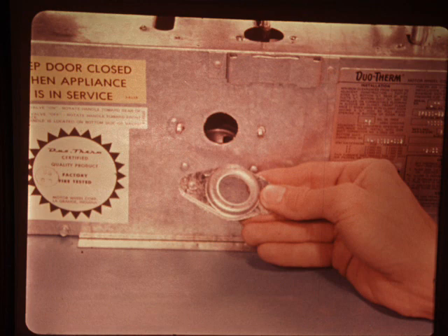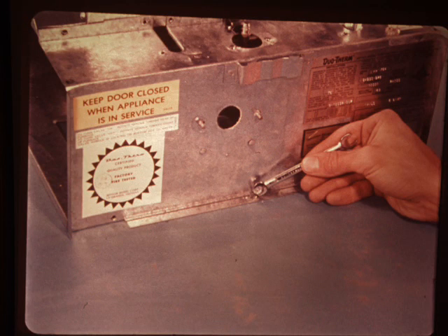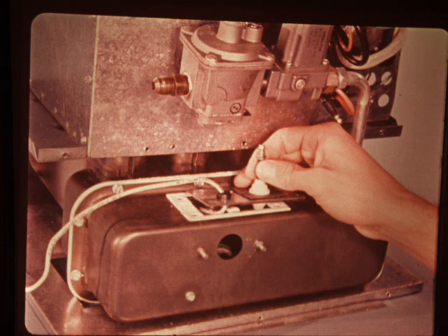Remove the sight glass and gasket. Now remove the front cover screws and the front cover. This gives you access to the igniter mounting screws. Take care that the igniter electrodes clear the burner orifices during removal. Move the igniter assembly to the right and tilt upward to remove it from the burner cover.